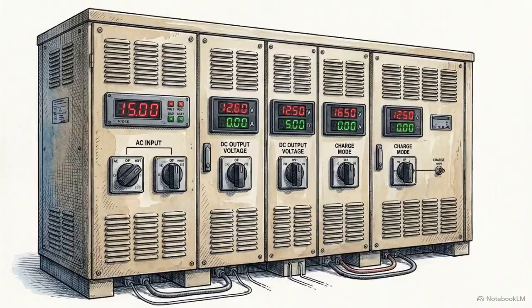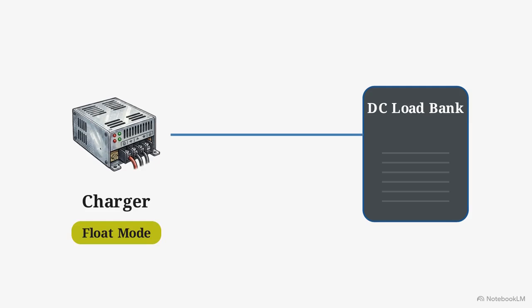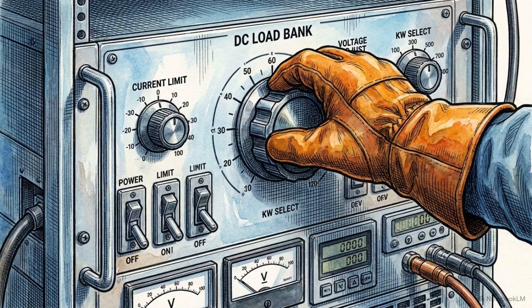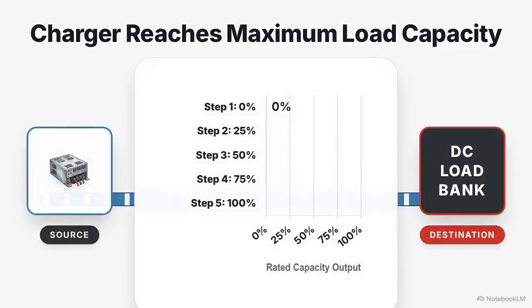With the chemical storage verified, the focus shifts to the active power electronics, the AC to DC battery charger. The charger is set to float mode, and the DC load bank is connected to its output to simulate variable grid loads. The unit is then stressed based on the simulated load through 5 stages: 0%, 25, 50, 75, and finally 100% of its rated capacity.